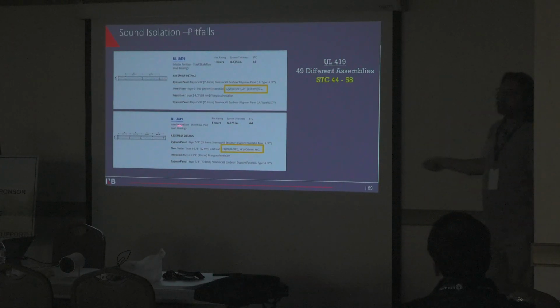The fire rating is absolutely the fire rating on a UL listing. The STC rating is more of a convenience that's provided sometimes when it's a single rating that's listed for multiple UL listings. So for example, UL 419 has 49 different assemblies that fall under that. Their STC ranges from 44 to 58. So just because you see a UL rating and that's the UL rating you're using for your assembly, you can't necessarily follow the STC that's listed for it unless you dig down and make sure that that is the correct assembly for that.